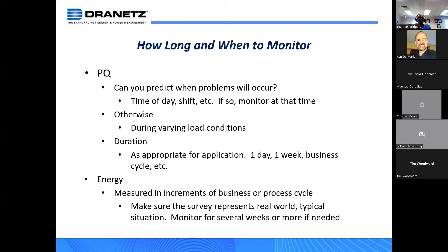How long and when to monitor for PQ? You might monitor until you record the event or something significant you think might be causing the problem. Monitoring surveys can be a week or a month — a month is more common especially if you're doing energy monitoring, because you want to match the billing cycle of the utility. Typically one week might be common, or even one day — you might find the results within one day.